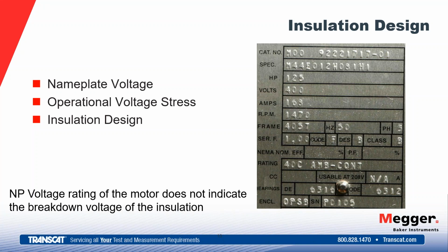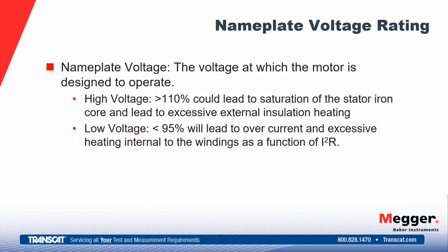So again, when we talk about high voltage, we're going to voltages as high as what that motor sees during these time periods. Nameplate voltage is the voltage at which the motor is designed to operate. So again, high voltage in that case would be considered 110% higher than nameplate. That's an issue if you have too high a voltage.